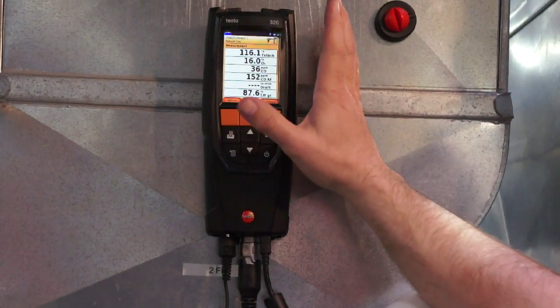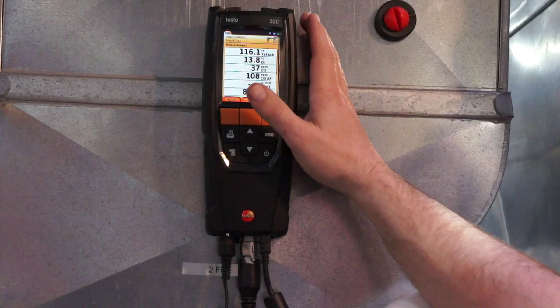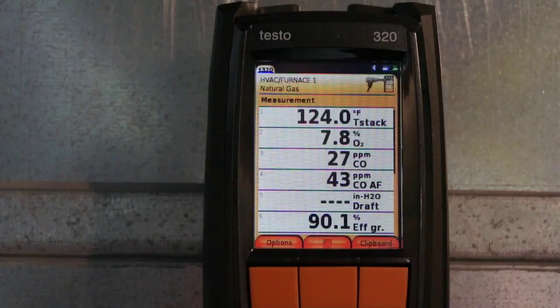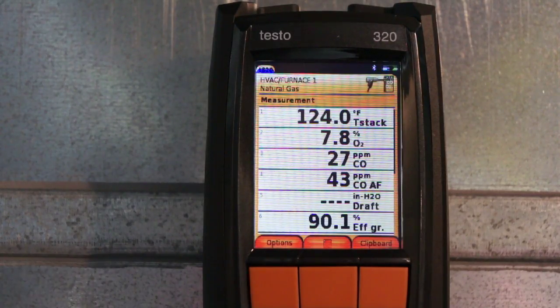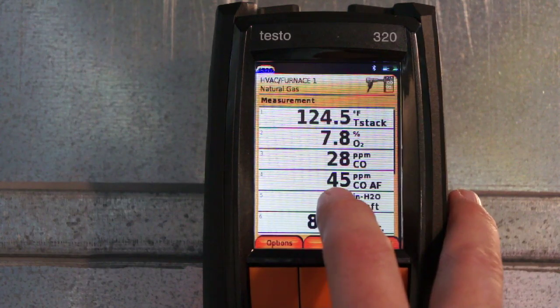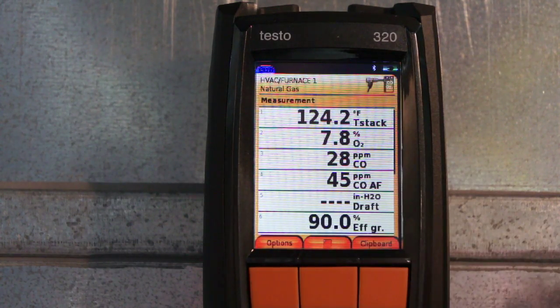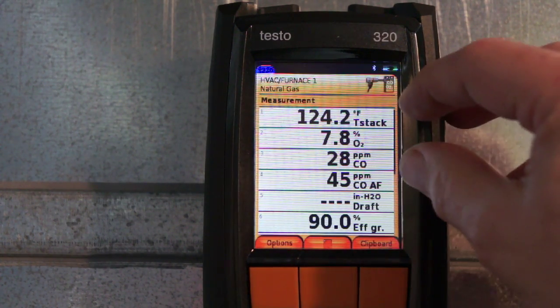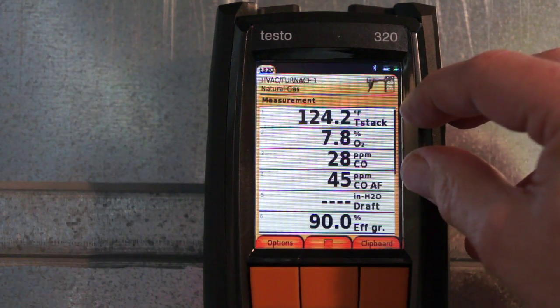I'm going to zoom in a little bit closer here in a second, and I'm going to walk you through some of the readings. I always get asked, what are you looking for when you do a combustion test? I want to start off with these first 4 readings on the analyzer: stack temperature, O2, CO, and CO air free. These are probably, in my opinion, the most important readings the analyzer makes, because they're the actual readings that are being measured. Everything else, aside from the first 3 measurements, is calculated on the analyzer.